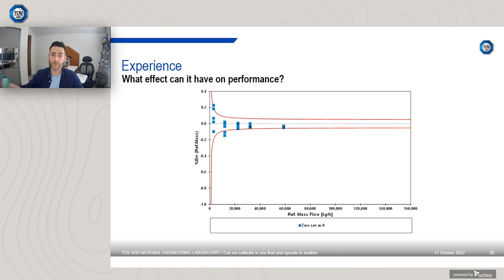So what effect can it have on performance? I have some data here where I've manually changed the zero for a Coriolis meter that we've calibrated. Again, on the x-axis I have reference mass flow in kilograms per hour. On the y-axis I have that deviation from the device under test, the Coriolis meter, with respect to the reference. Here we have set the zero as 0, so ultimately I've applied no zero correction at all. And this is the data.